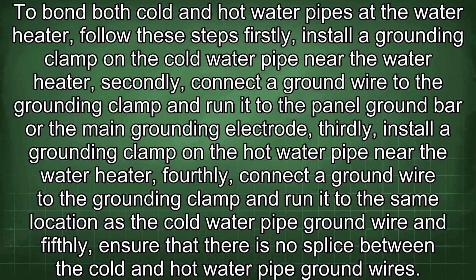Firstly, install a grounding clamp on the cold water pipe near the water heater. Secondly, connect a ground wire to the grounding clamp and run it to the panel ground bar or the main grounding electrode. Thirdly, install a grounding clamp on the hot water pipe near the water heater. Fourthly, connect a ground wire to the grounding clamp and run it to the same location as the cold water pipe ground wire. And fifthly, ensure that there is no splice between the cold and hot water pipe ground wires.